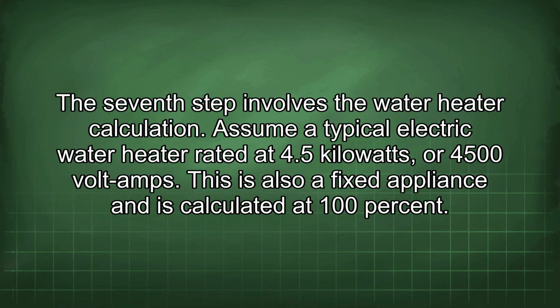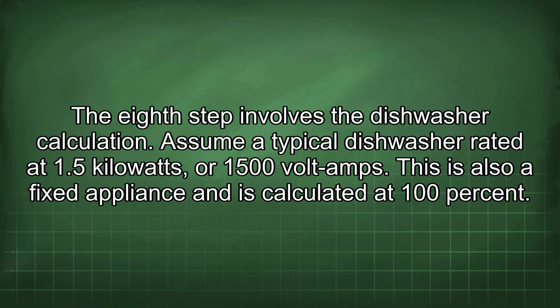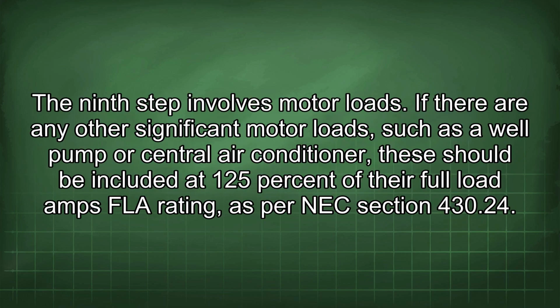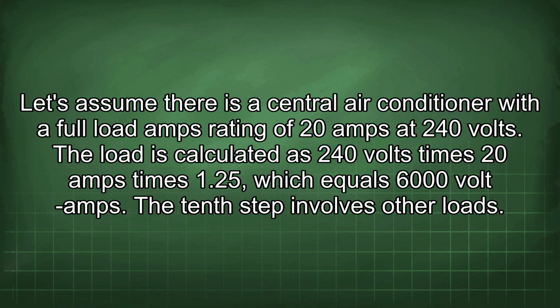The seventh step involves the water heater calculation. Assume a typical electric water heater rated at 4.5 kilowatts or 4,500 volt amps. This is also a fixed appliance and is calculated at 100%. The eighth step involves the dishwasher calculation. Assume a typical dishwasher rated at 1.5 kilowatts or 1,500 volt amps. This is also a fixed appliance and is calculated at 100%. The ninth step involves motor loads. If there are any other significant motor loads, such as a well pump or central air conditioner, these should be included at 125% of their full load amps (FLA) rating, as per NEC section 430.24. Let's assume there is a central air conditioner with a full load amps rating of 20 amps at 240 volts. The load is calculated as 240 volts times 20 amps times 1.25, which equals 6,000 volt amps.